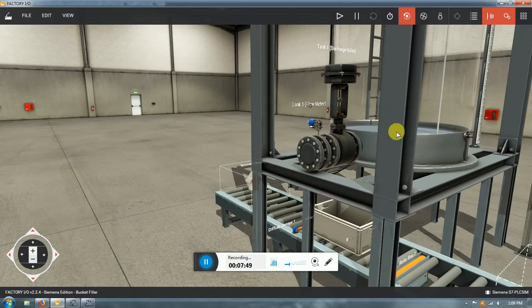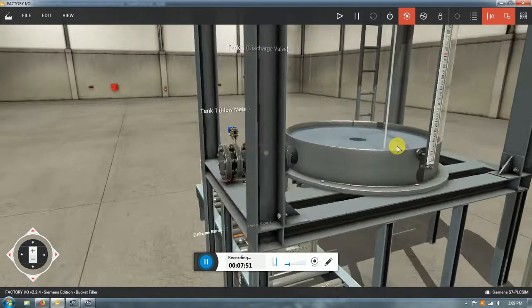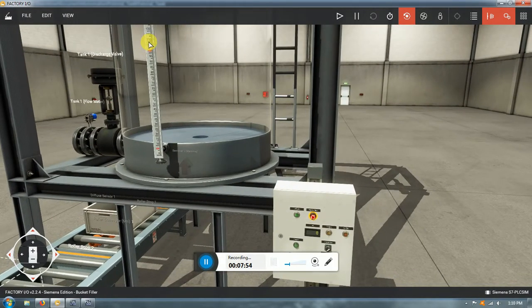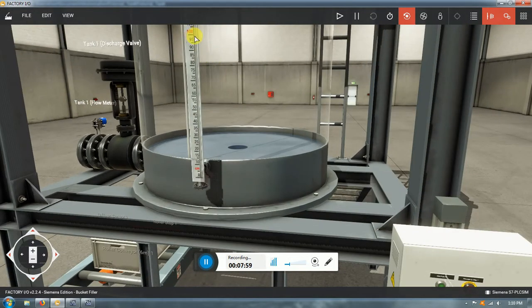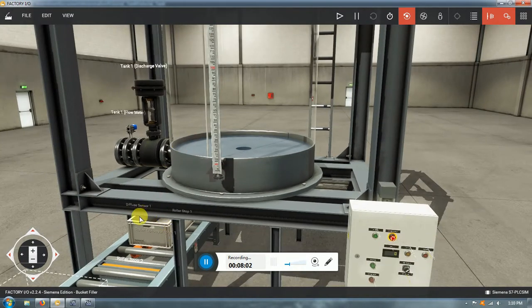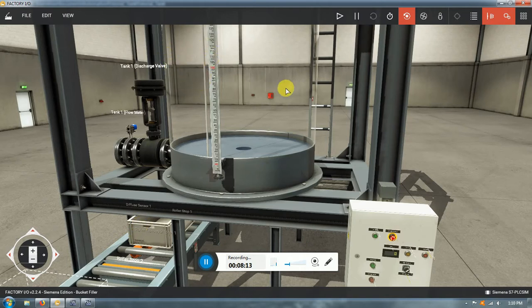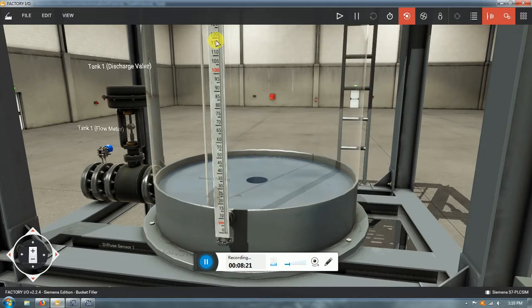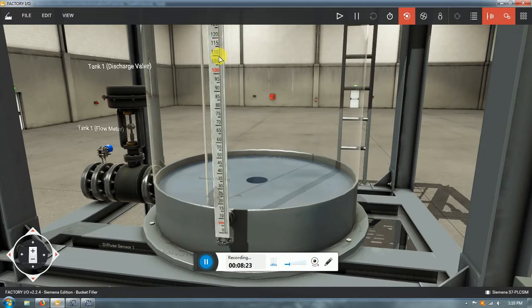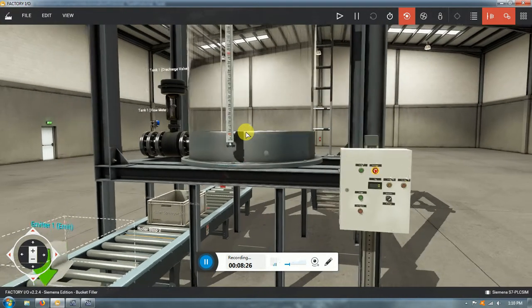That forced me to use the flow and the level as measurements. I control the level, and when it drops a fixed amount — about four or five centimeters — that drop in level is enough to fill one container. Because the tank's cross-section is constant, a fixed level change always corresponds to the same volume. So between 60 and 65 cm is the same volume as between 110 and 115 cm.